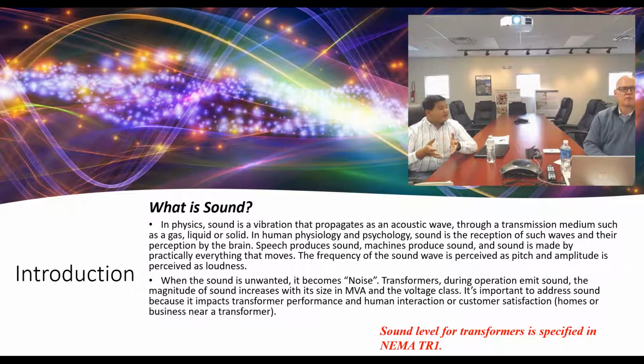The transformer during its operation emits noise mainly, and the magnitude of the noise increases with the size of the transformer. Based on the MVA and the kVA rating, the noise level of a transformer increases. There is a guideline, NEMA TR1, which provides the limits for the specific size of the transformer, and based on that we design. But nowadays substations are located in close proximity to residential or commercial areas in cities, mainly where we have really limited space. So at that particular place, it becomes essential to reduce or limit the noise emitted by the transformer.